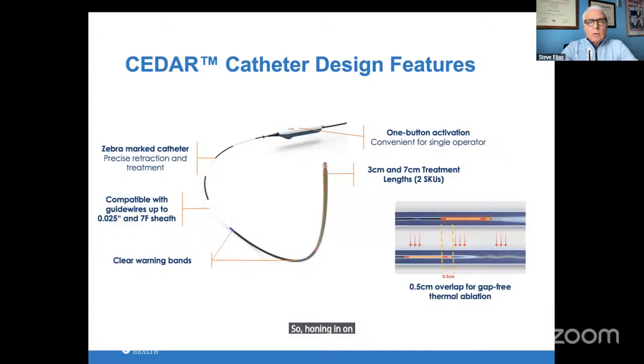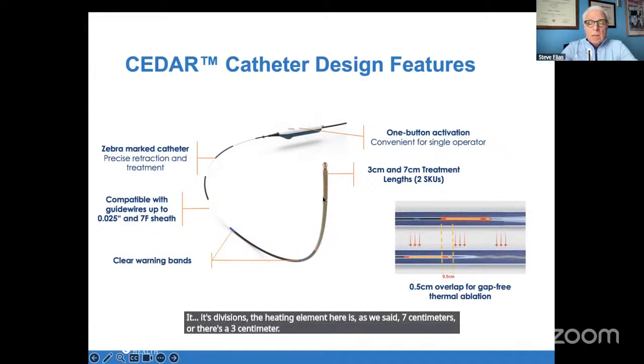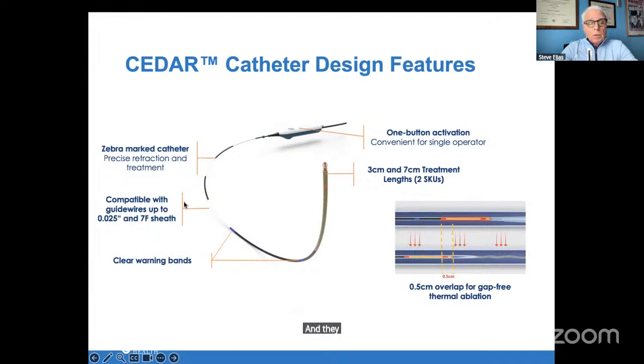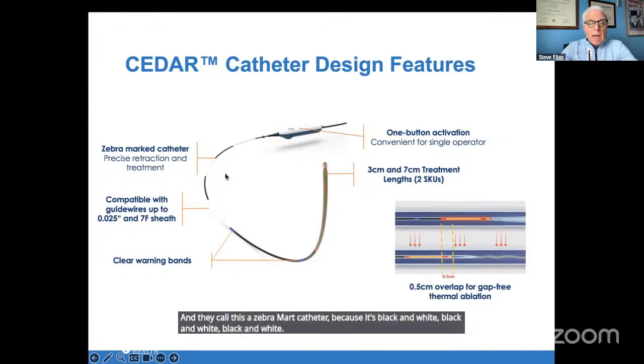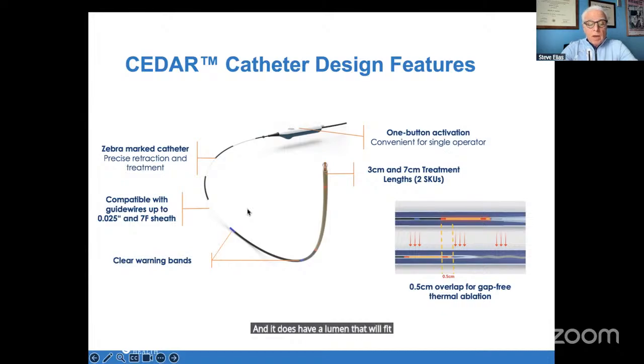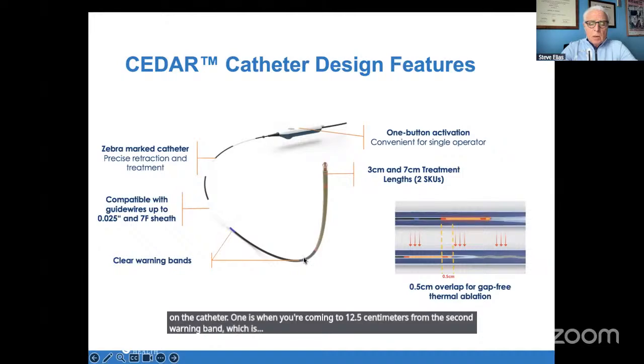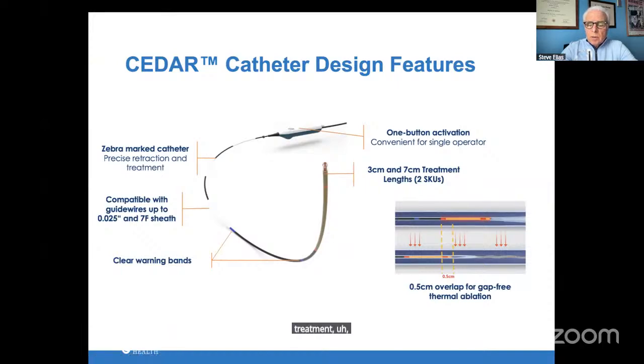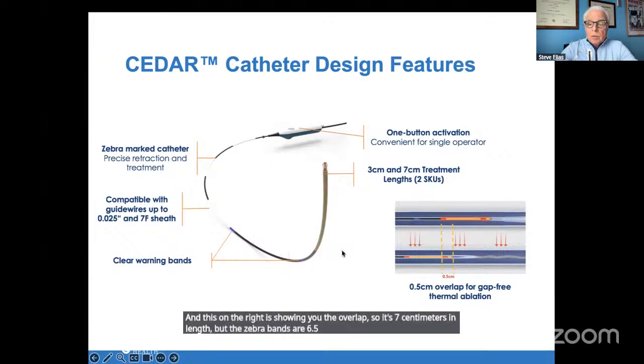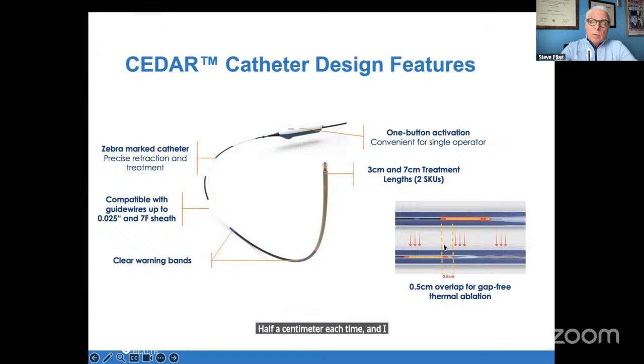So honing in on the catheter, its divisions, the heating element here is, as we said, 7 centimeters, or there's a 3 centimeter heating element length as well. And they call this a zebra marked catheter because it's black and white, black and white, black and white. And it does have a lumen that will fit up to an 025 wire if needed. And there are warning signs, warning bands on the catheter. One is when you're coming to 12.5 centimeters from the second warning band, which is, you can see, very close to the heating element. So when you see the second warning band, you know that's your last treatment for that patient. And this on the right is showing you the overlap. So it's 7 centimeters in length, but the zebra bands are 6.5 centimeters. So you're overlapping 0.5 centimeter each time. And I know all this sounds familiar to what we have out there already with some of the catheters.